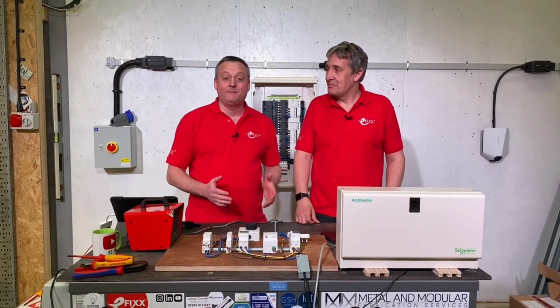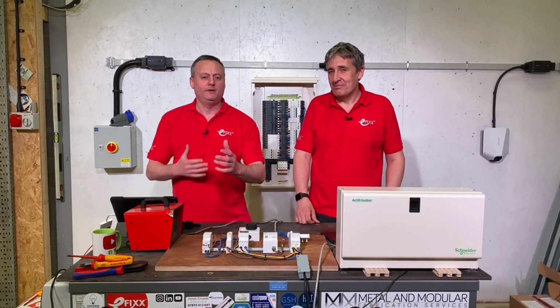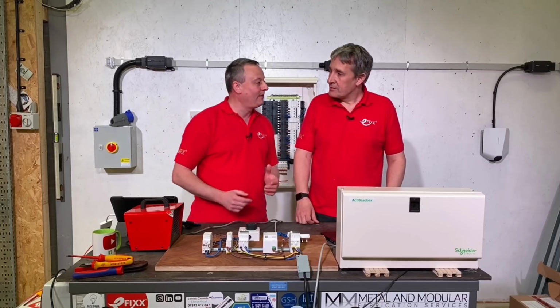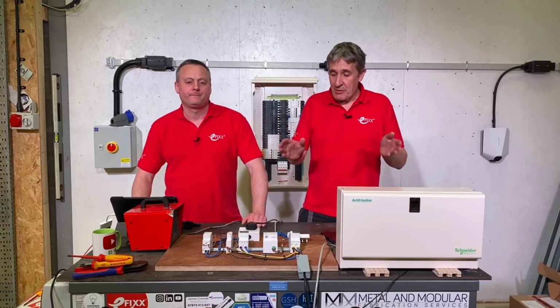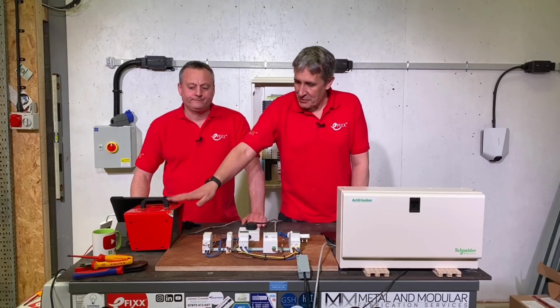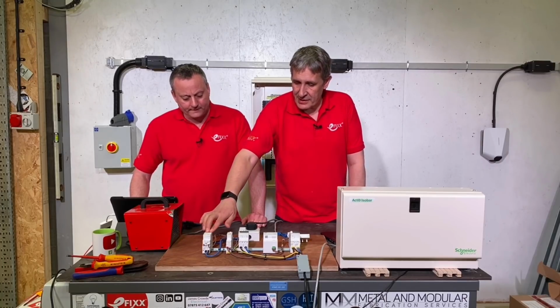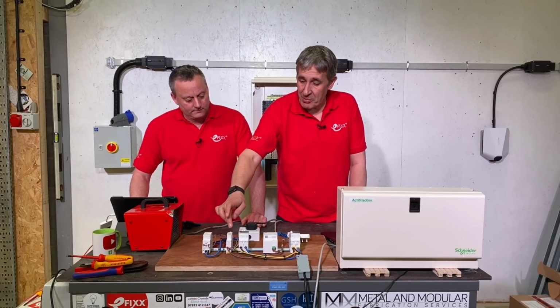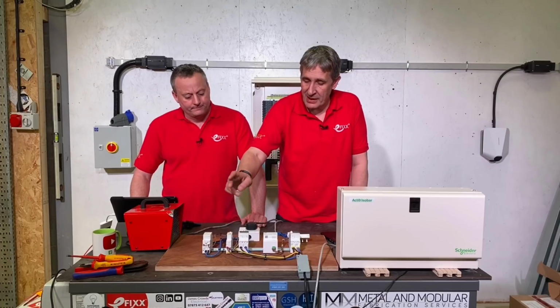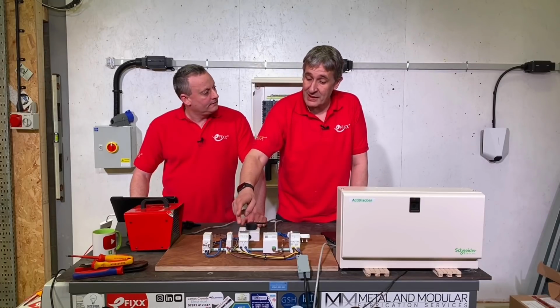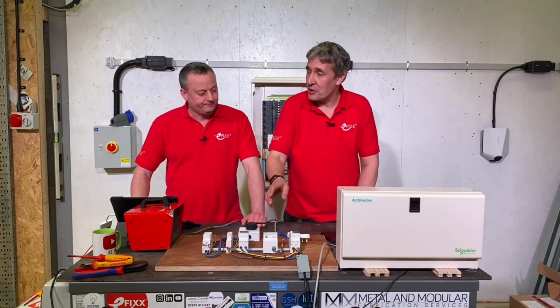That clearly demonstrated how easy it was to fit the PowerTag, but you said it can measure power, so now you'll show how it measures that output. On our demo rig, we've got a heater on the bench connected through the contactor, controlled via the input-output module of the system, and connected through the PowerTag on the end of this 40 amp circuit breaker.